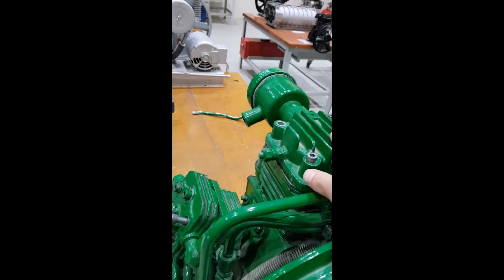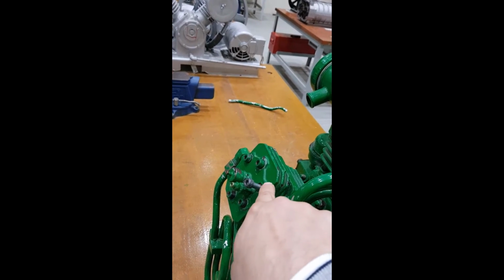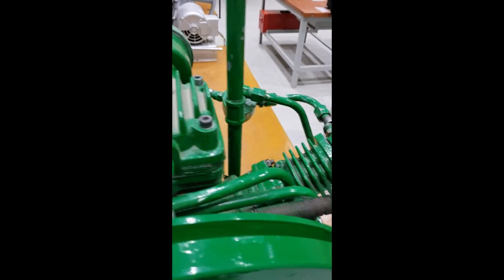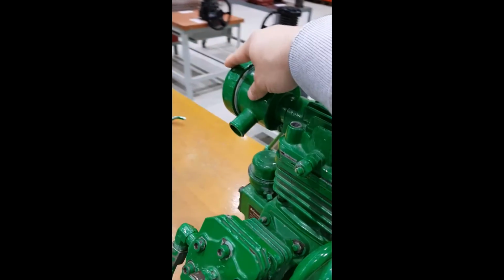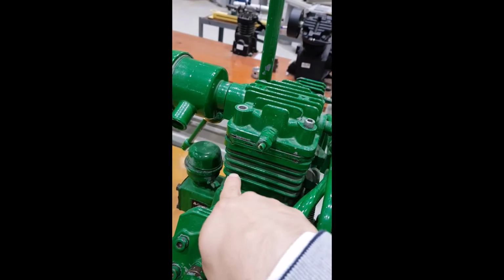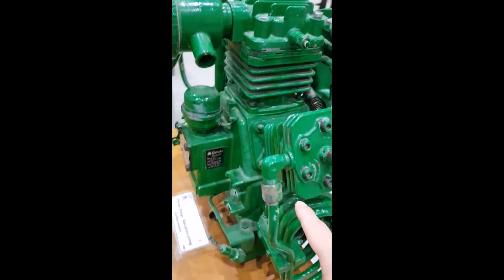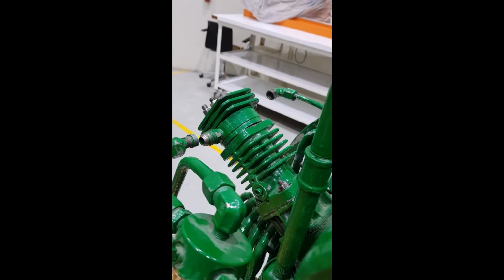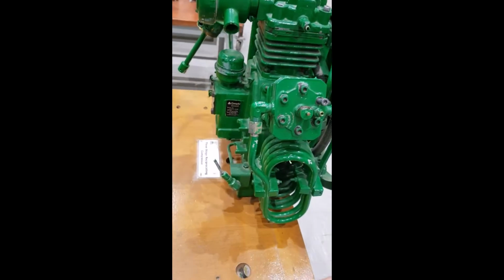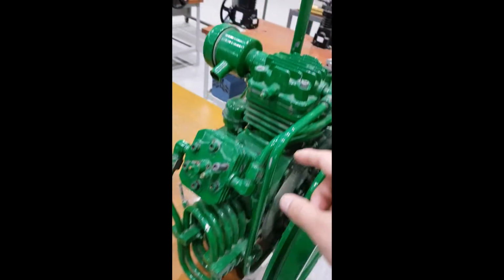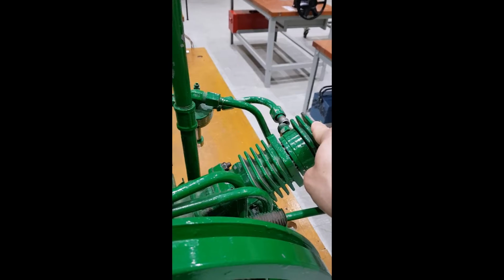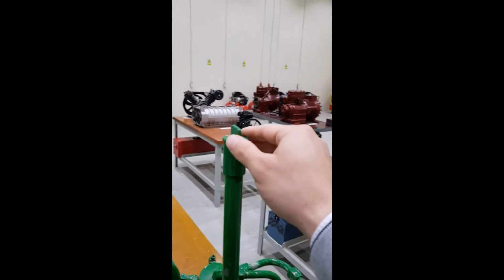So this is the first, which is LPC. You can consider this one to be HPC1 and this one HPC2. Now the components: we have the filter, the cylinder head, and the cylinder block. Again here we have the second stage cylinder head and cylinder block. In the third stage, similarly, we have a cylinder head and cylinder block in this area. What we have in our three-stage reciprocating compressor is that the first two cylinders are pistons, and the third one is a plunger.